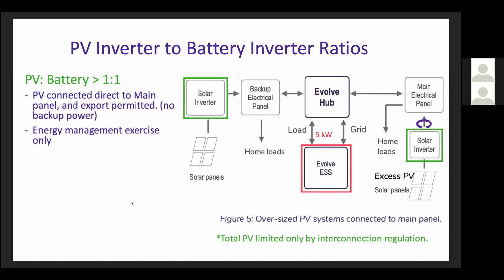So again, with that PV inverter to battery inverter ratio, when the PV to battery ratio is greater than 1-to-1, some of the PV is connected directly to the main panel when export is permitted. That excess PV, as I mentioned, as far as splitting up that array, will not be a part of the backup loads panel and charging the battery when the grid is down. And again, as shown here, this little CT symbol, that little circle, is to stress that all of the PV needs to be measured while grid tied, not just the PV that's going to serve the backup loads when in off-grid mode. So we've got to measure all the PV while grid tied in order to maximize charging of the battery during normal operation.